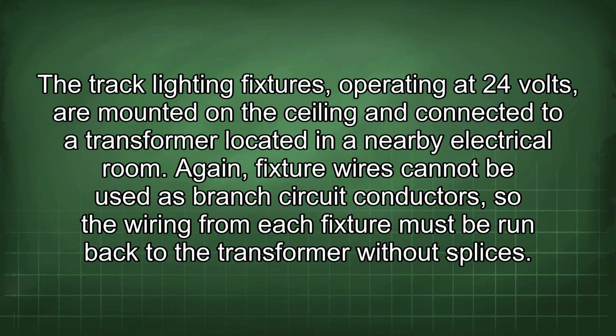The track lighting fixtures, operating at 24 volts, are mounted on the ceiling and connected to a transformer located in a nearby electrical room. Again, fixture wires cannot be used as branch circuit conductors, so the wiring from each fixture must be run back to the transformer without splices.